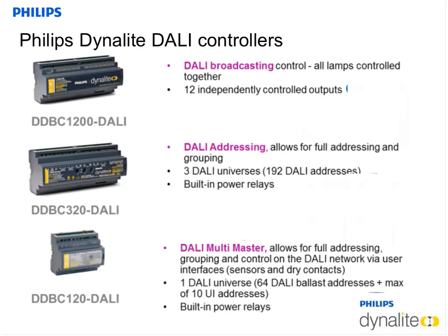We have broadcasting, which is probably the simplest but the most labor-intensive type of DALI. We then have addressing, which is the first opportunity to use addressing in a room environment. And then we have DALI Multimaster, which you've probably heard of. This is a fully digitally controlled, almost minimum wired solution, which I'll show you in the next slide.